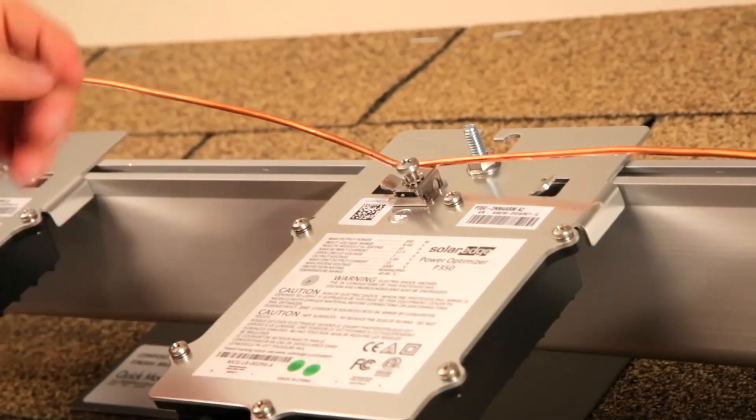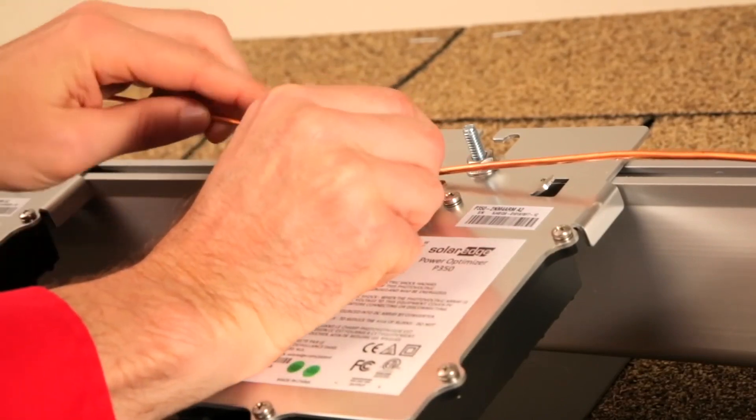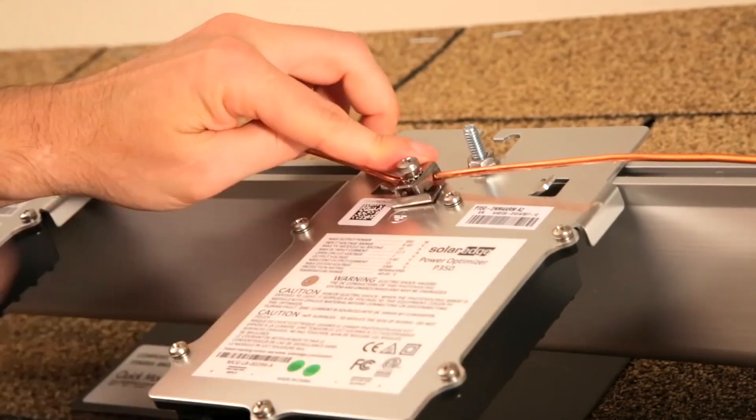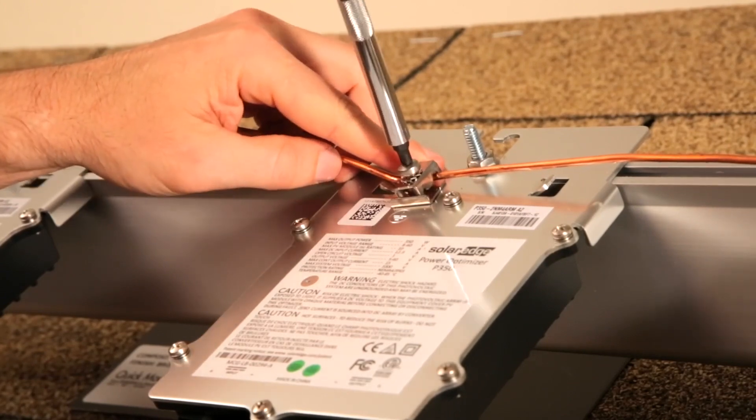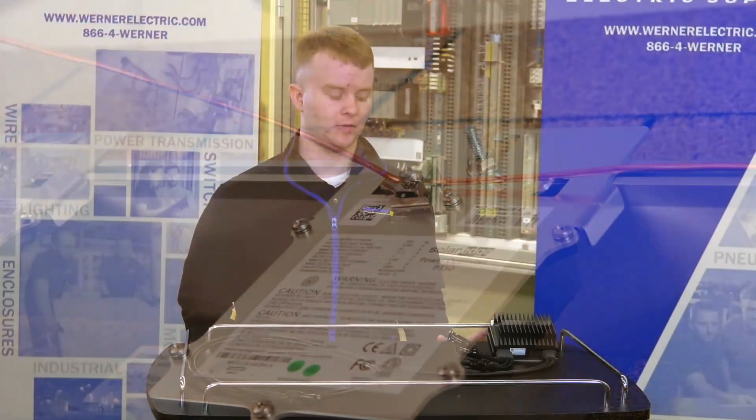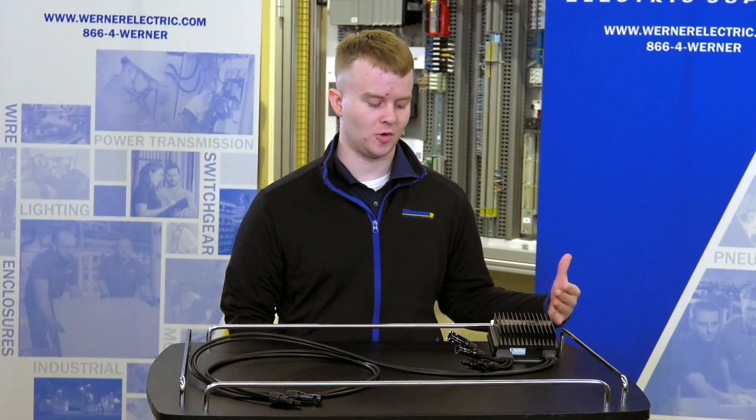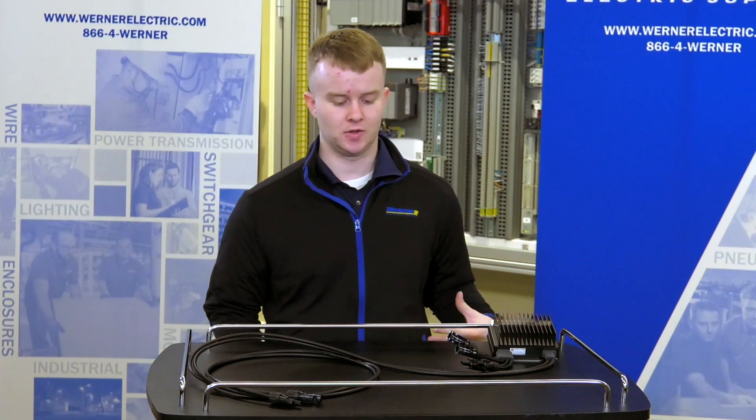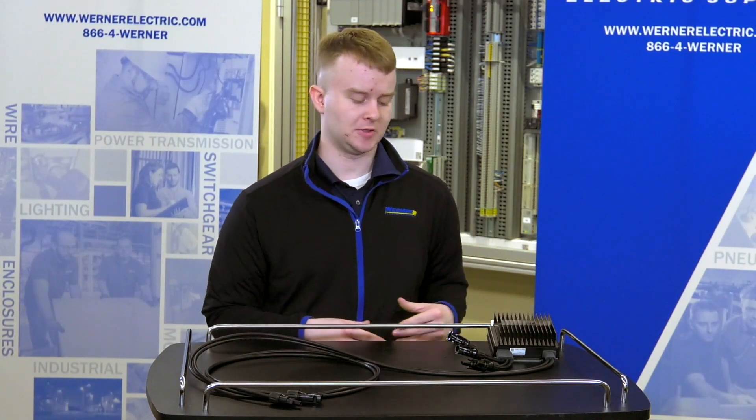The P860 optimizer is perfect for solar modules that have regular current outputs between 8 to 10 amps. For lower current modules you would actually want to use the P800P optimizer, but today we are seeing more modules being used at the regular levels, which is why I'm introducing the P860.